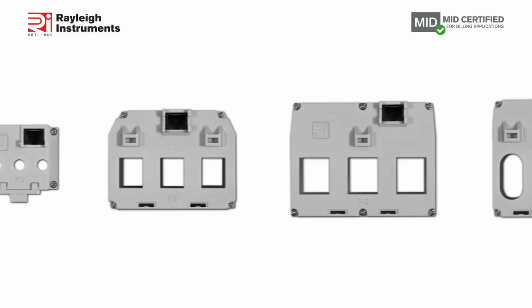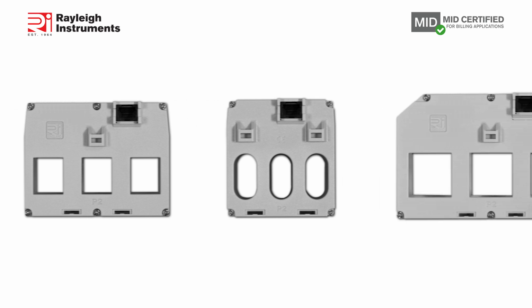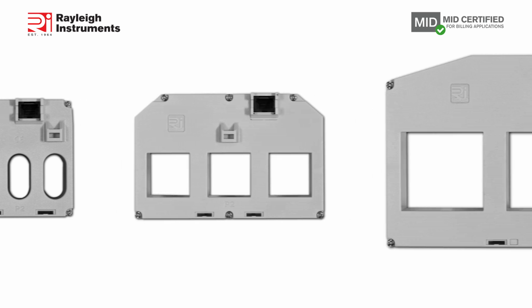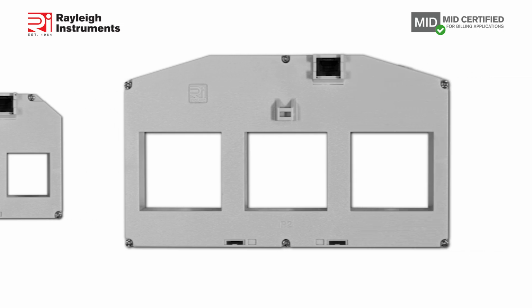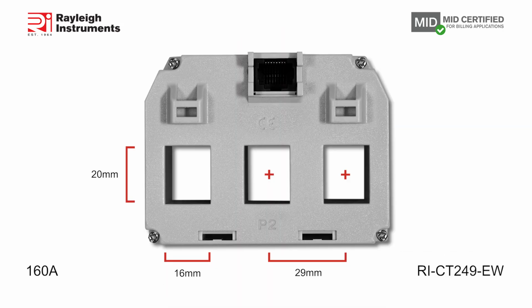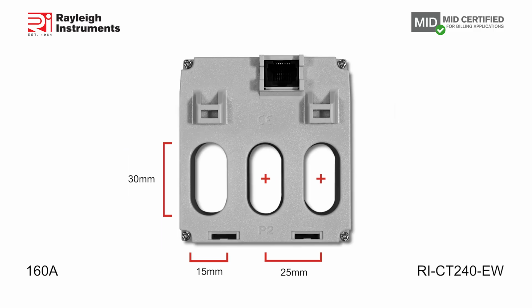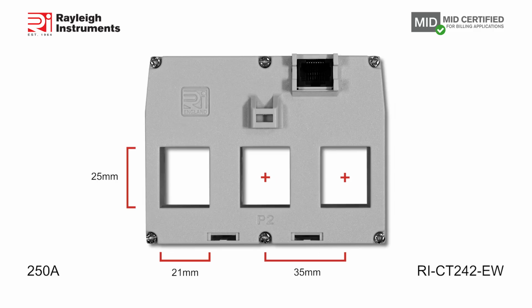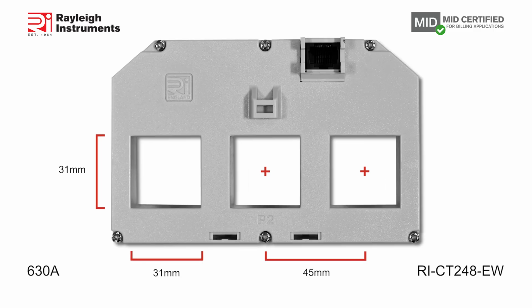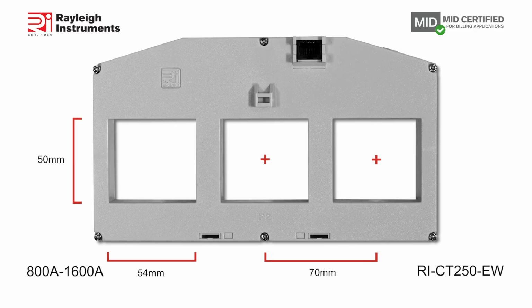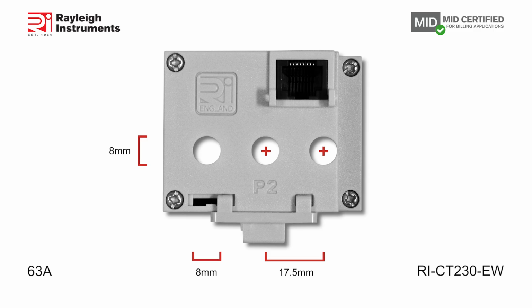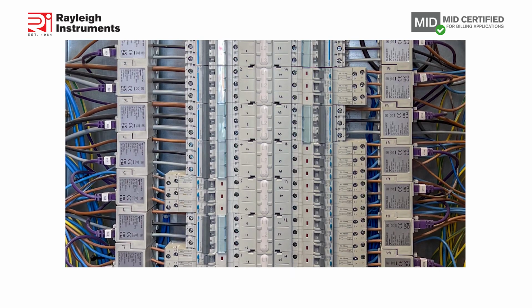The current transformers in our range monitor primary currents from 32 amps up to 1600 amps and come in 6 frame sizes. We have 2 frame sizes for 160 amp breakers, 1 frame size for the most popular 250 amp breakers, 1 frame size to fit 630 amp breakers, and a frame size for 800 amp to 1600 amp breakers. We also have the baby of the bunch, which has been designed for 63 amp single or 3-phase loads with an interlocking design to fit the tight spaces in distribution boards for branch monitoring.